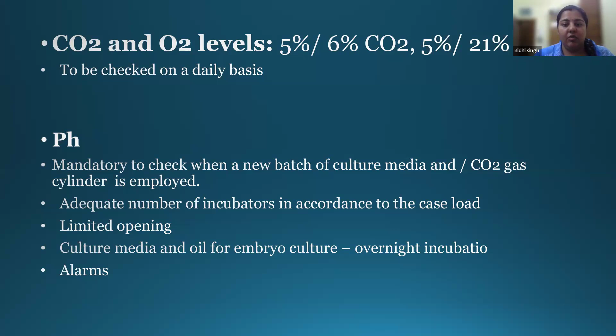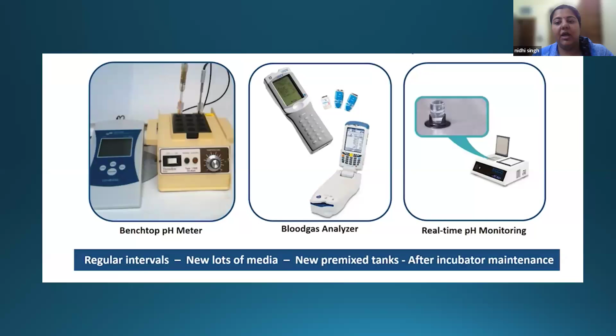Also, one of the important points is to use oil overlay. If you are having an incubator and you use an oil overlay, it benefits in a way that the evaporation is not very fast, the osmolarity does not change very fast, the temperature is lost comparatively less, and the pH change is comparatively slower as compared to when the embryo culture is not overlaid by oil. And finally, the alarms. Alarms should always be there. Now, these are the various pH meters which are being used. One is a benchtop pH meter, there are blood gas analyzers, and also the real-time pH meter.